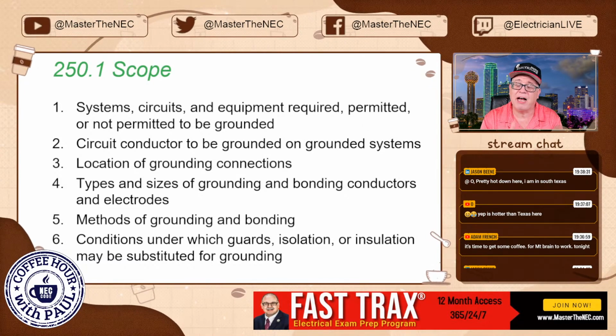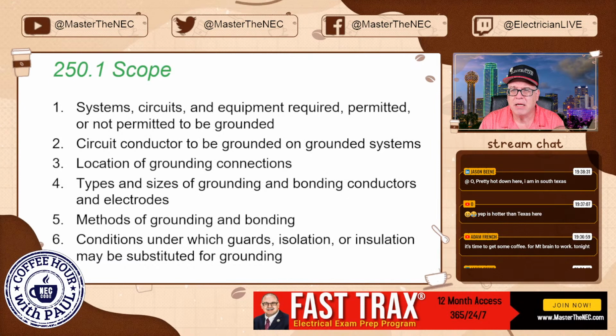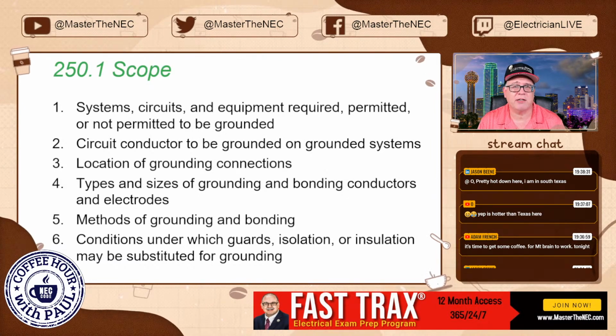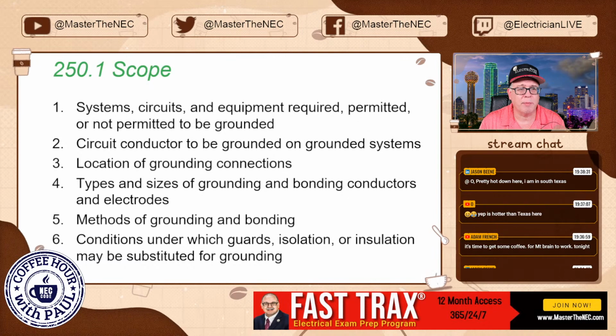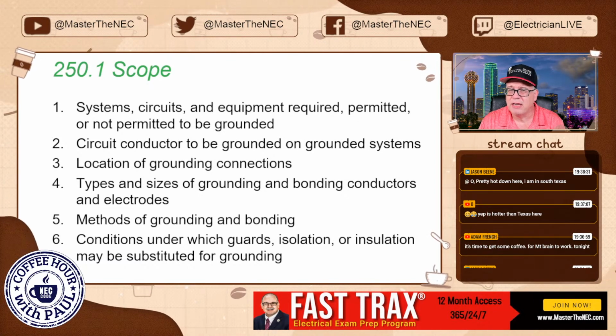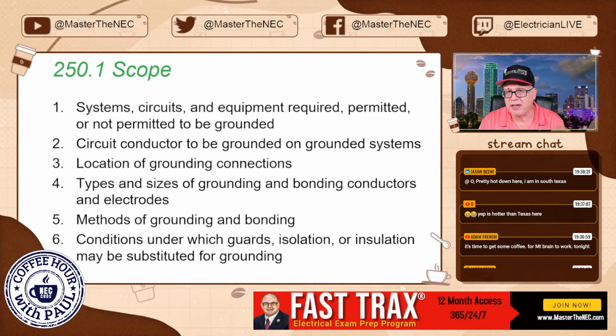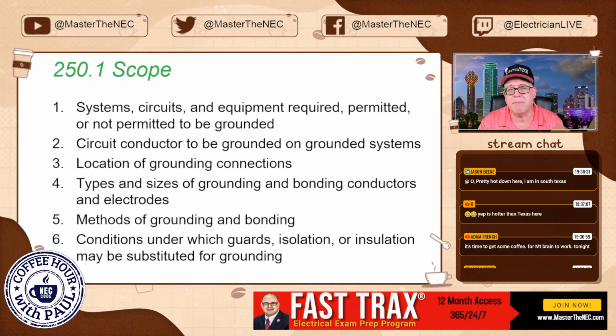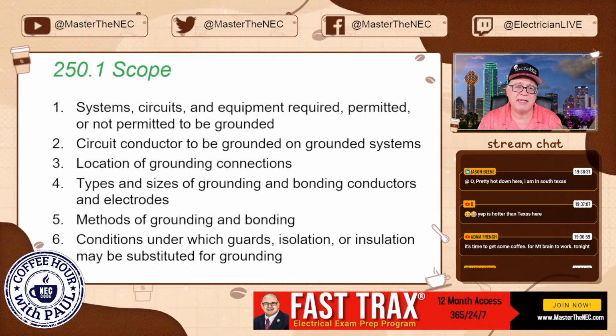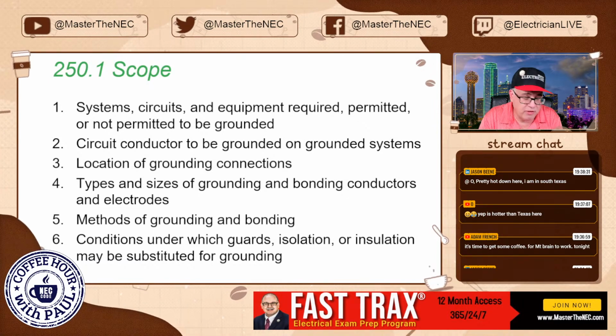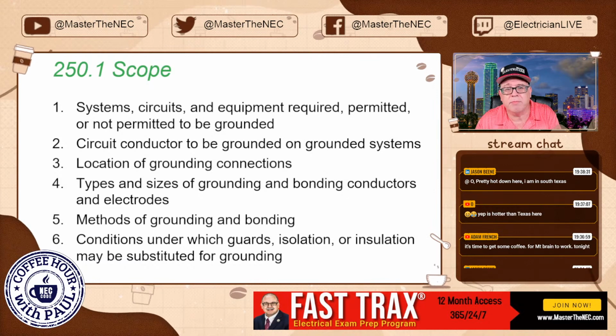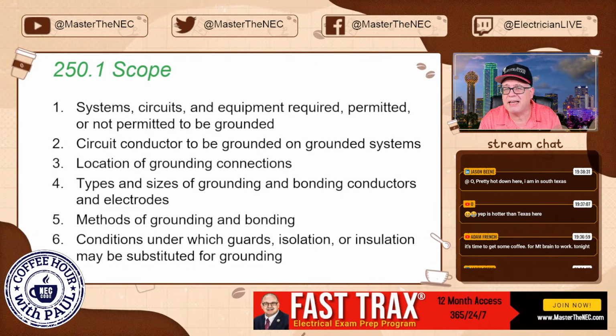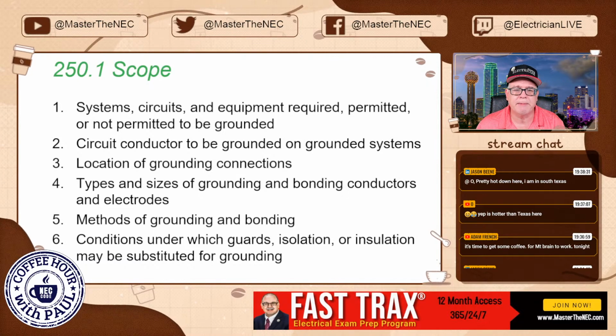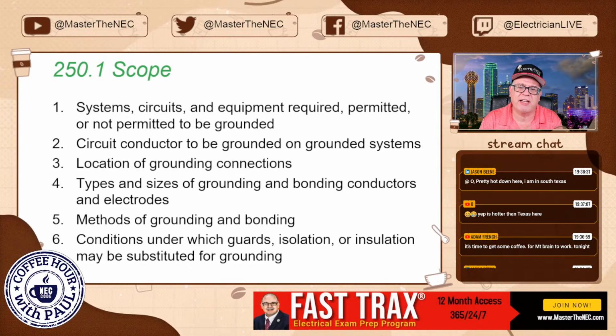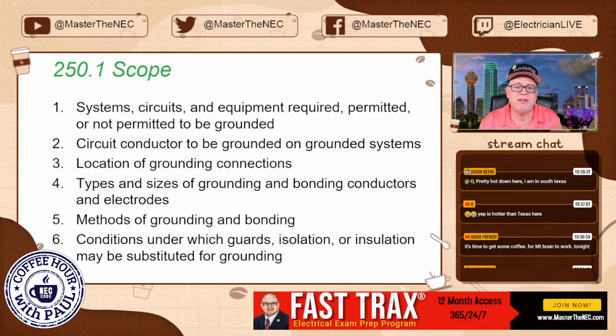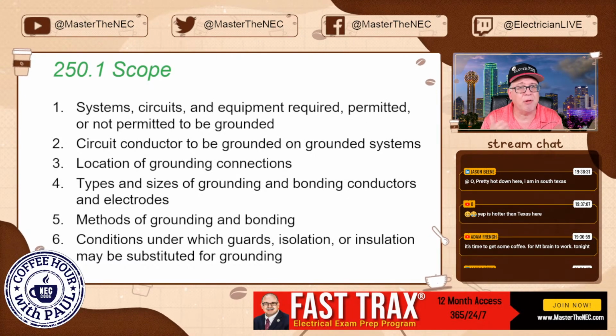We also, item number 5, talk about the methods of grounding and bonding. Interesting is that an equipment grounding conductor is there to clear an overcurrent protective device, but it also extends that connection and gives you that reference to earth and helps stabilize the voltage, especially when you're reading it with meters and things like that. An equipment grounding conductor can serve double duty, right? It's bonding, but it also serves a grounding component. And there are certain methods of terminating and all these kinds of things that are covered in 250. Conditions under which guards, isolation, or insulation may be substituted for grounding, like double insulation.